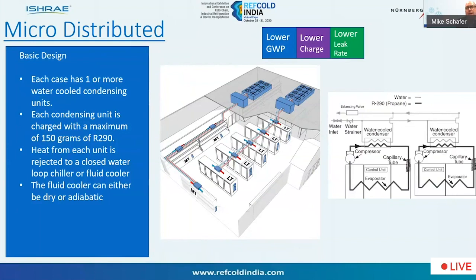Heat from each of the units is rejected through a plate heat exchanger in a closed water loop system. And the fluid cooler or chiller, the fluid cooler can be either dry or adiabatic. So once again, it's a very simple system, utilizing cap tube as the expansion device typically.